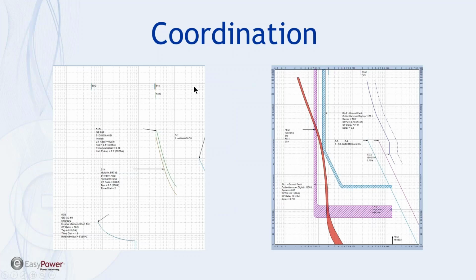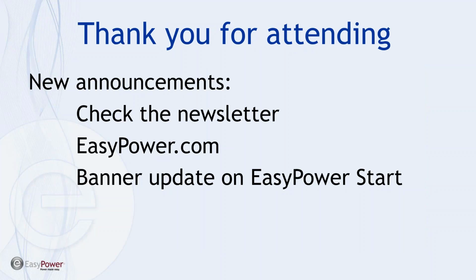What we've learned is that probably the trickiest part of using the Power Protector module is making sure we're looking at a fault which is examining only the ground fault currents. And so we have to pick out either a single line to ground or a dual line to ground. And based upon that, we can make adjustments and coordinate the ground fault protection, both for a hard grounded and a high resistance grounded system.